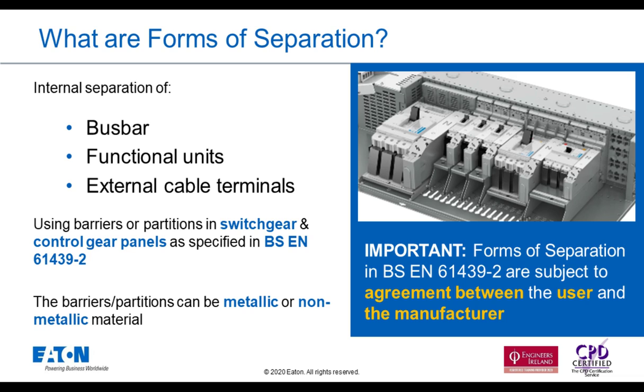One important clause to remember is that forms of separation in the current standard are subject to an agreement between the user and manufacturer. Now, what this means is that there are various ways of achieving the same form of separation, different methods, different techniques. So that clause is really just to say that it's ultimately down to the user and manufacturer to agree on what method is the best method suited to them.